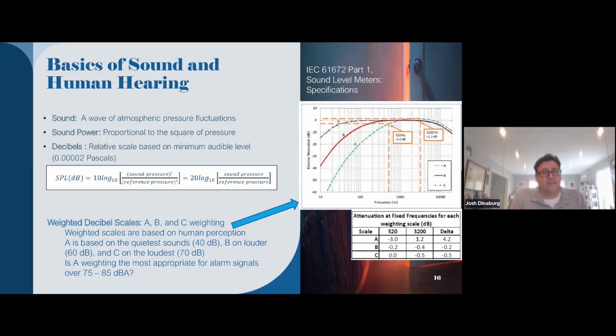So we actually rate these in some different scales. The one you'll usually see is dBA. That is the way smoke alarms are currently required to be tested for their audibility. You can see they have slightly different ratios compared to just the raw decibels, which is the power. If you look at dBA, it actually slopes down pretty far here at these lower frequencies, which basically means you get a penalty at those lower frequencies to have the same A rating as the raw decibel rating.